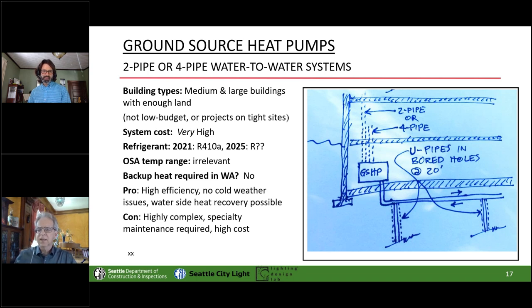But like I said, this might be where we need to go over time. And then you don't care in the winter how cold it gets. There's always heat, heat and heat and more heat. And that heat pump is living its best life at 50 or 55 degrees off the ground loop. So you don't worry that it's 5 degrees outside. This is the thing we're going to do, if we ever get a net zero Montana project.